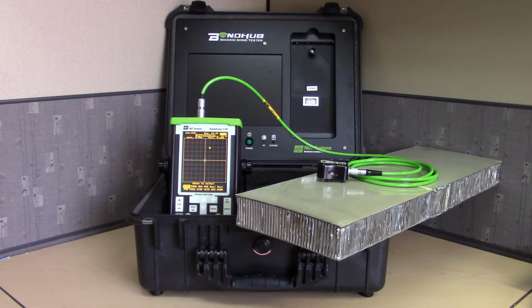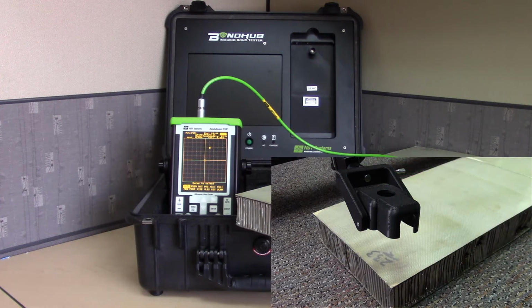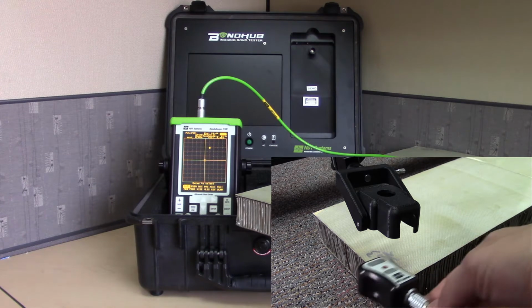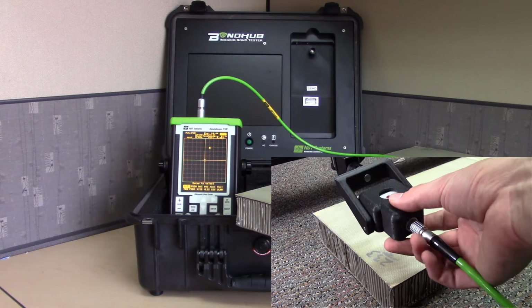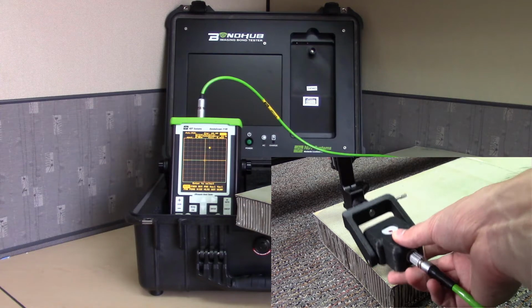First step, calibrate your BondaScope for use on this particular sample, or whichever sample you're using. For information on how to calibrate the unit to a sample, please refer to our BondaScope setup video. Once you've calibrated the BondaScope to the sample, go ahead and set up the probe for use on the scanner by connecting it to the probe holder. Set the probe holder down onto the sample and align for scanning.